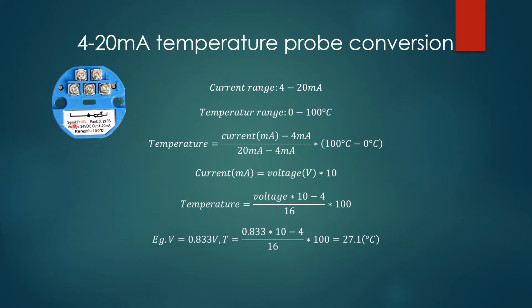It needs this particular signal from this PT100, a platinum sensor probe, and it wants these three wire connections from the sensor to this transducer. It will only take temperature within 0 to 100 degrees C, and it will convert that into a range of 4 to 20 milliamps. So that's what it does. It reads that temperature range and converts it into this current range.